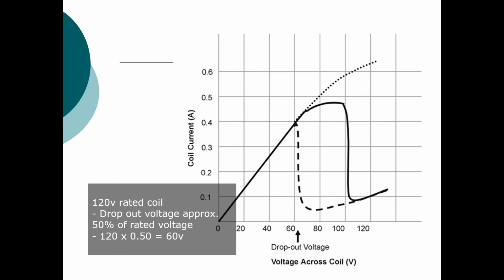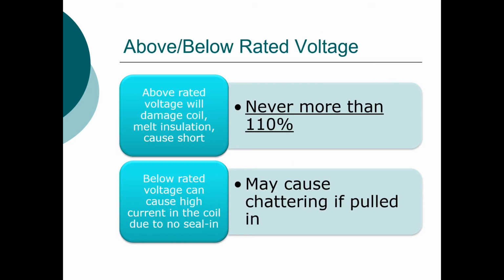By understanding both the pull-in and the drop-out voltage of our relays and contactors, we can always make sure that our systems are operating within that limitation. And it is important to get our voltage to our coil as close to the rated voltage as we can. Just as we can understand how having too little voltage to my coil could cause problems, we can also have problems by applying too much voltage.